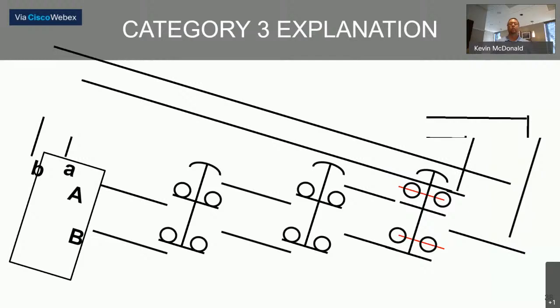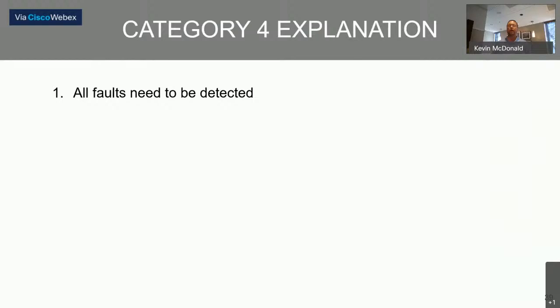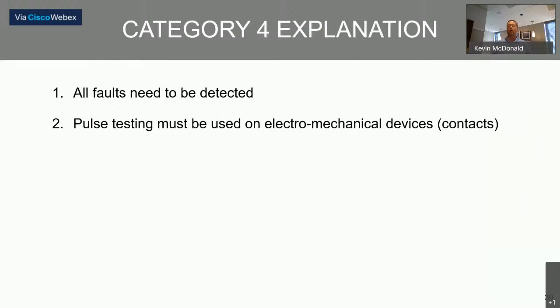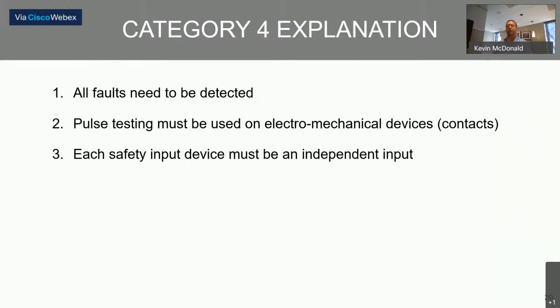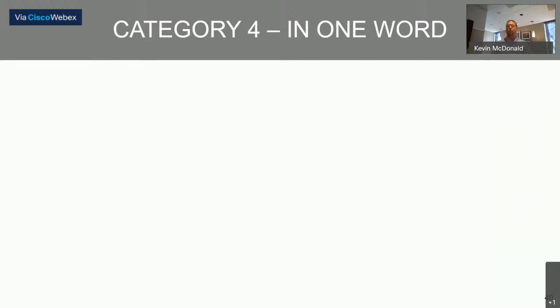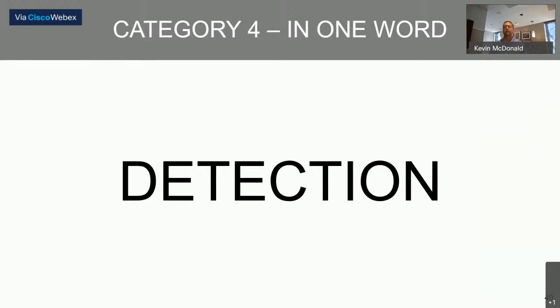To summarize the main differences between Category 3 and Category 4: Category 4 requires (1) all faults must be detected — no single fault or accumulation of faults can defeat the circuit; (2) pulse testing must be used on electromechanical devices — this detects shorts between channels; (3) each safety input device must have an independent input — no daisy chaining. One word for Category 4: detection. Gary Smith and Benjamin LeBay also correctly guessed Category 3 on that last circuit — great job to all.